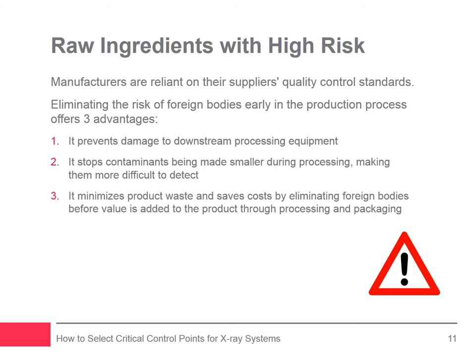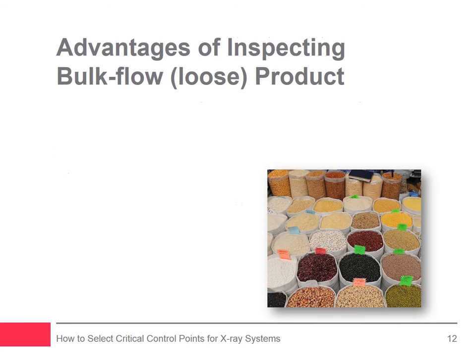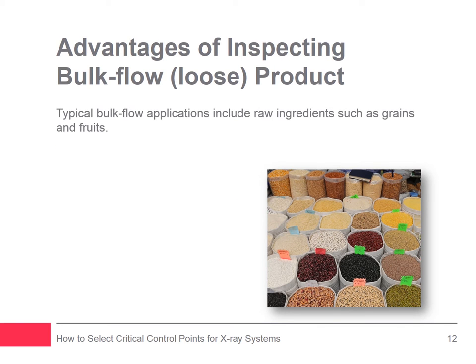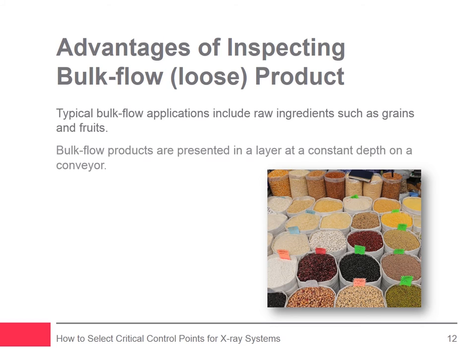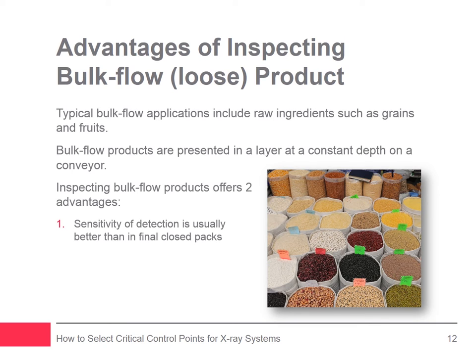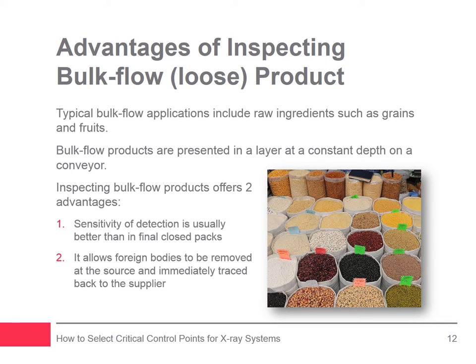Typical bulk flow applications include peanuts, extruded snacks, dry fruits, vegetables, sweets, and pulses. Bulk flow products are presented in a layer at a constant depth on a conveyor, typically 25 millimeters or less. This shallow depth offers outstanding levels of sensitivity for x-ray inspection — up to four times more sensitivity than inspecting finished packs. That's why it's worth thinking about placing an x-ray system early in the process where it can inspect incoming goods or raw materials. It allows foreign bodies to be removed at the source and immediately traced back to the supplier.